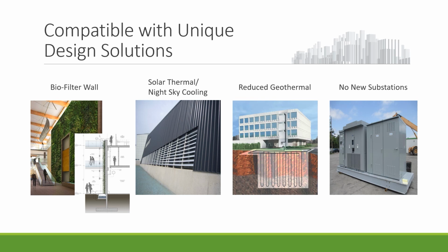No new substations needed. An example is a building being constructed in standard fashion with various energy-consuming efficiency components, like ice storage. The designers found they did not have enough electricity coming into the building for the existing substation, and would have to add an additional substation to manage electricity for the building and its components. When they used integrated ventilation design, they realized less electricity was needed and didn't need the extra substation. That's a savings of several hundred thousand dollars right there in construction.